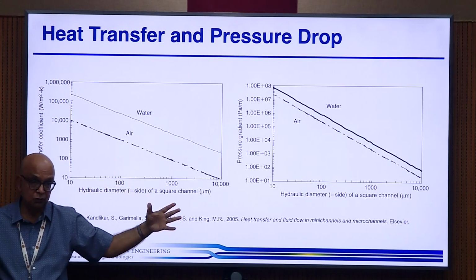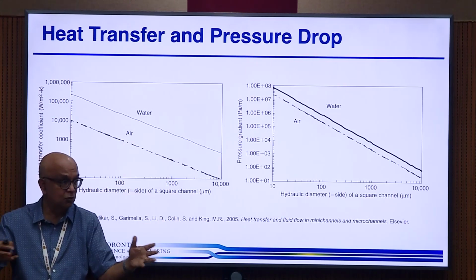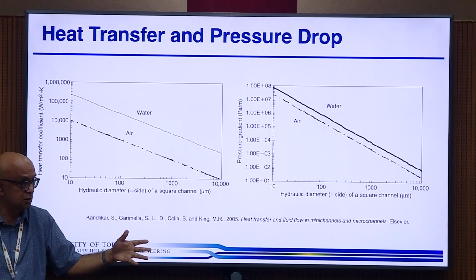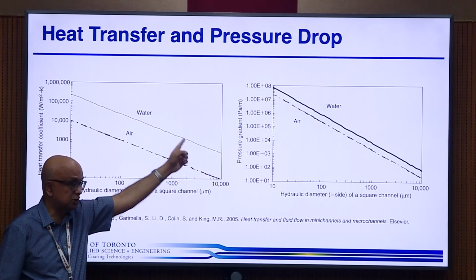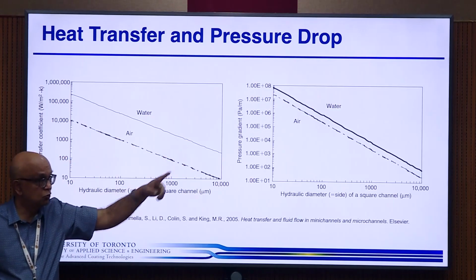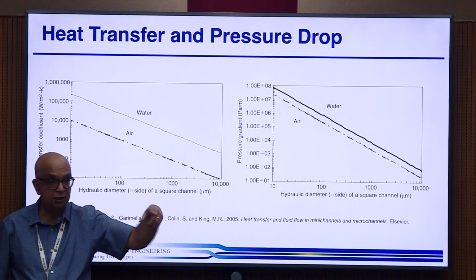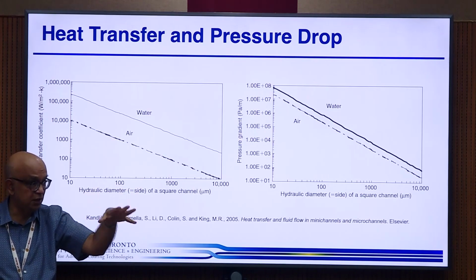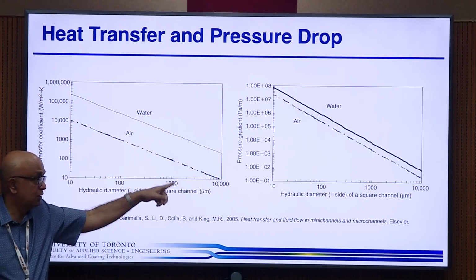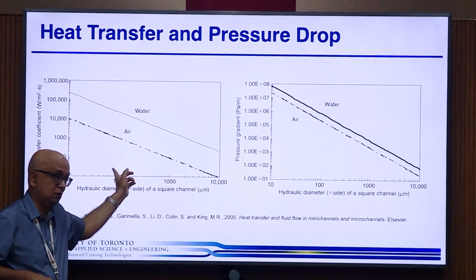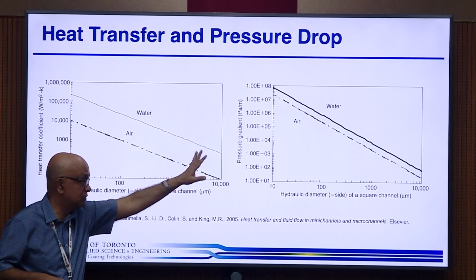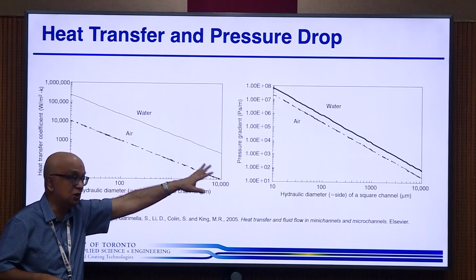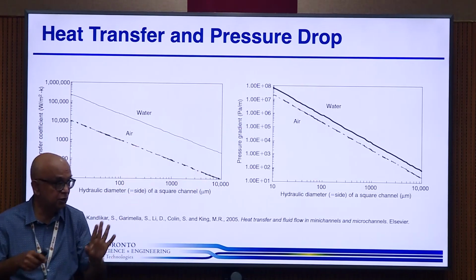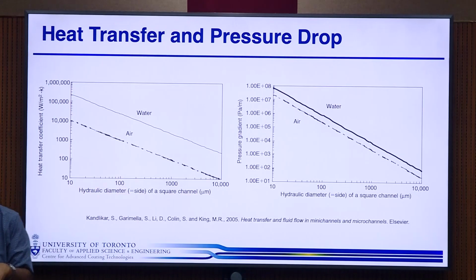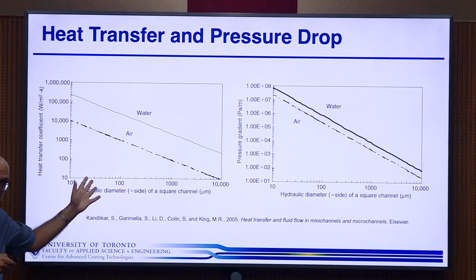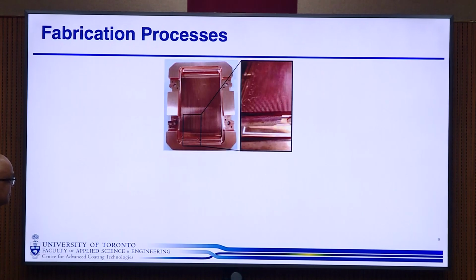So in theory, instead of having one big channel, you want lots and lots of small channels. Of course, the limitation is that your pressure gradient is also going up, so your pumping power is going up, and all of that power is being dissipated as heat inside your heat sink. So you could end up generating more heat than you're removing, and you want to keep that about 2 or 3% of your total heat removal. That is a very important parameter, and it limits how small you can make your channels.